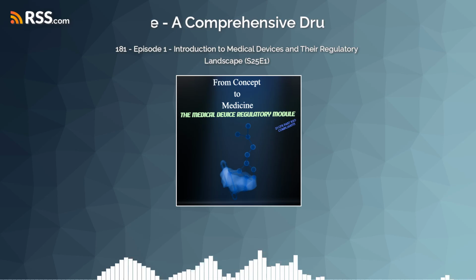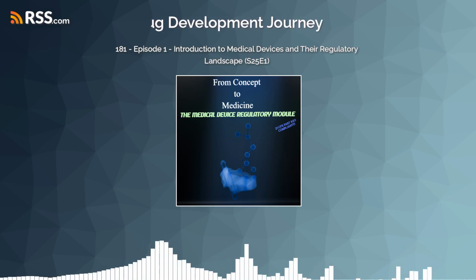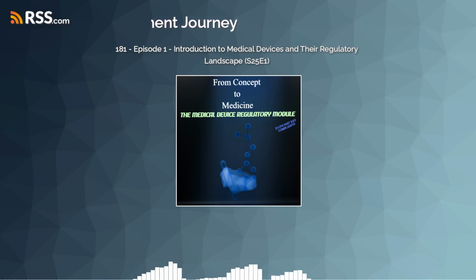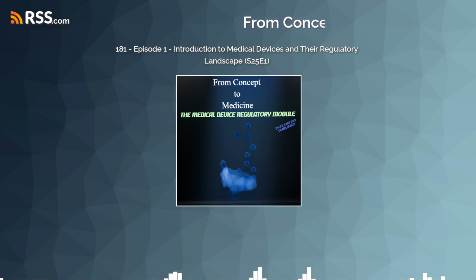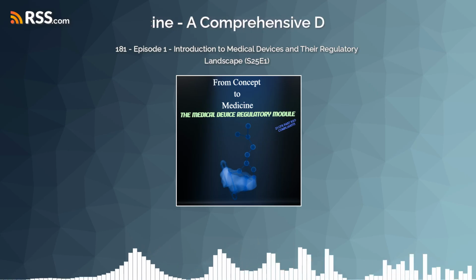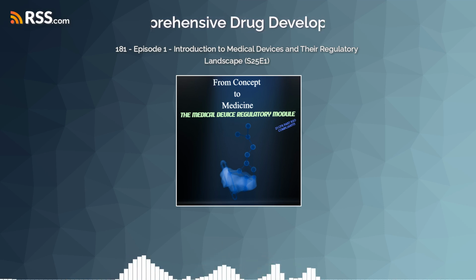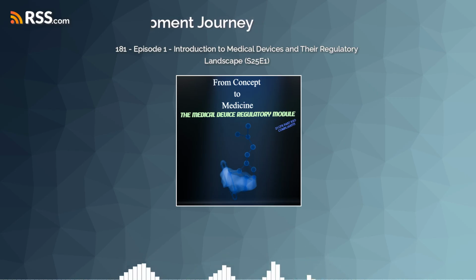Okay, proactive monitoring. And separate from that, but related, are the medical device reporting, or MDR, requirements under 21 CFR Part 803. Manufacturers and importers and device user facilities are required to report certain adverse events to the FDA. What kind of incident? Particularly if they become aware of information suggesting that one of their devices may have caused or contributed to a death or serious injury, or if a malfunction occurred that could lead to death or serious injury if it were to recur. It's about mandatory vigilance for safety signals.